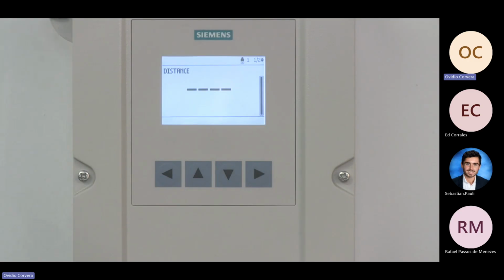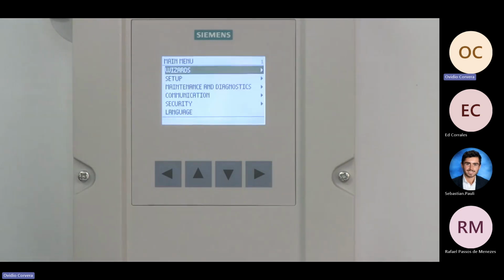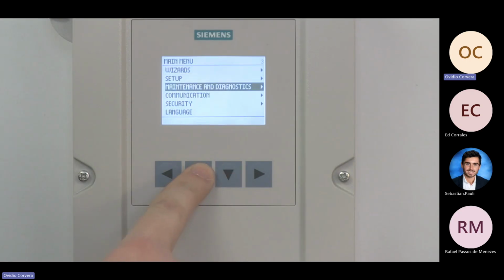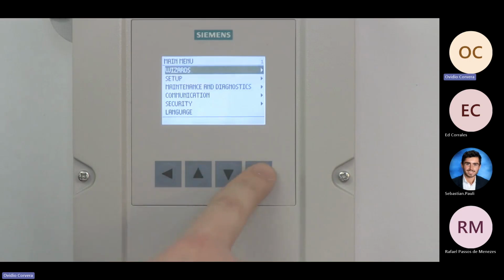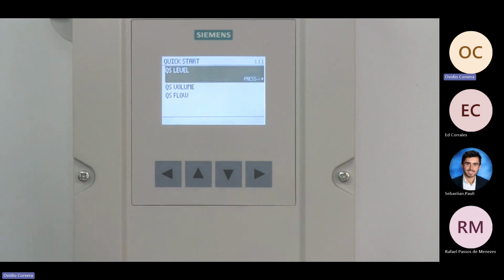Now, to enter program mode and configure the device using the Quick Start Wizard, press the right arrow. Once in program mode, you will see the main menu. You can scroll up and down with the arrows to view menu options. Highlight the Wizard's option and press the right arrow to select. The Wizard's menu has 2 options. Select the Quick Start by pressing the right arrow. Today, we are configuring the Level Quick Start Wizard. Highlight QS Level and press the right arrow to select. Press the down arrow and select Start.